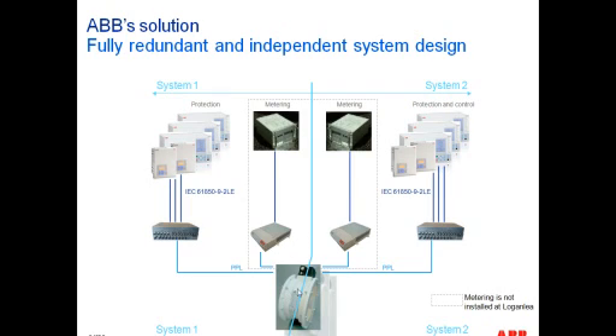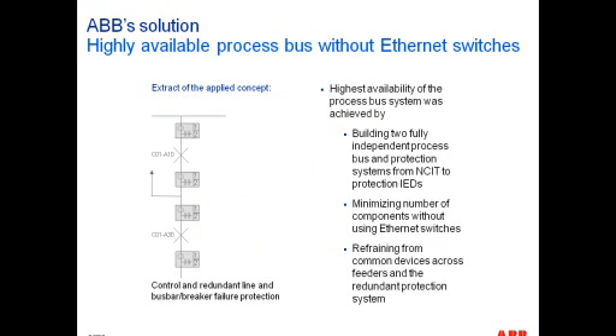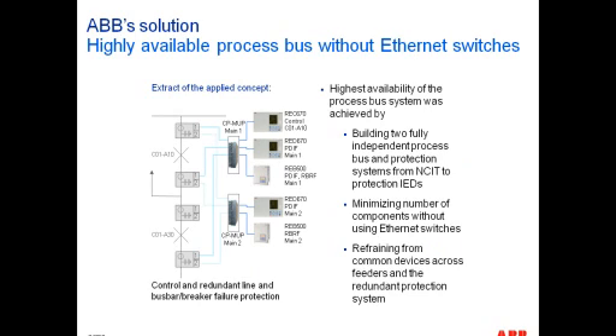Okay, and in the case of this particular system, essentially we had full redundancy up to the sensor level. So sensors were not redundant, but the electronics on the sensor are redundant, which then allowed us to interface redundantly to two different merging units and 2 different sets of relays, set A, set B, process bus network. And as described, this same concept was essentially applied for this ring bus, where at the process bus level, we did not use Ethernet switches. We used the available ports on each one of the merging units to feed information off to each individual device.